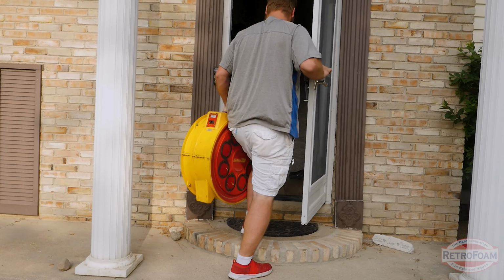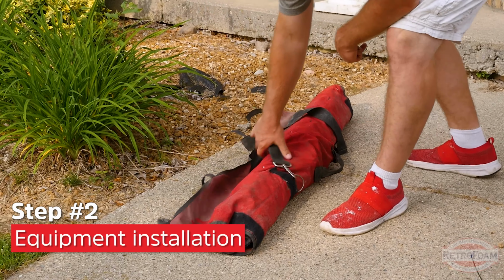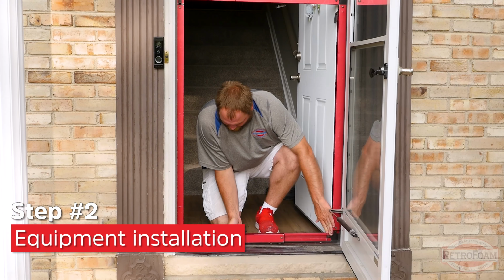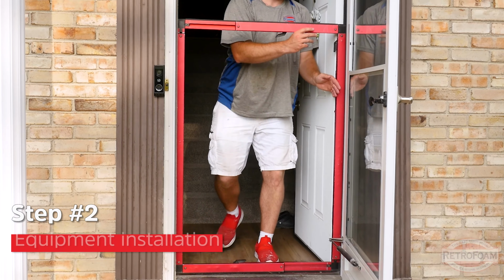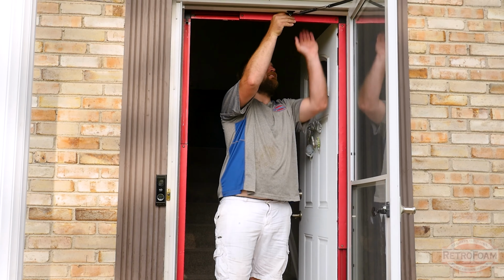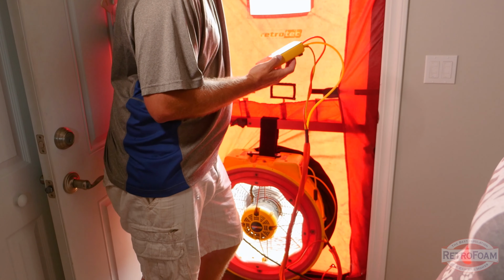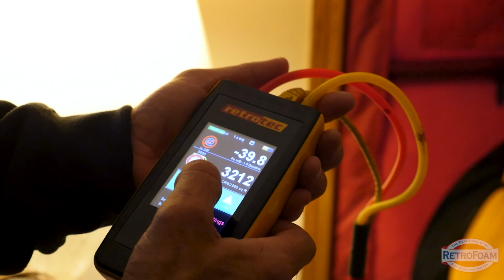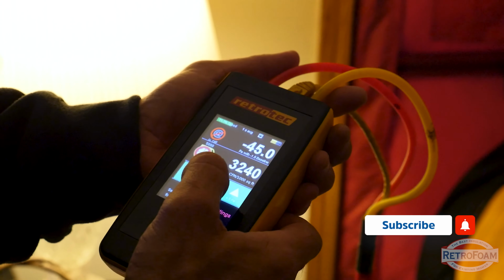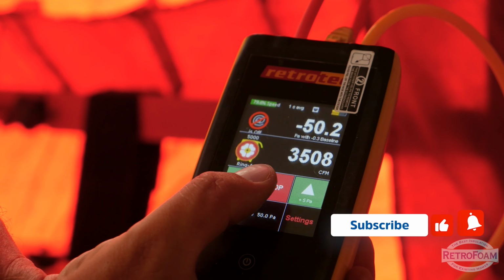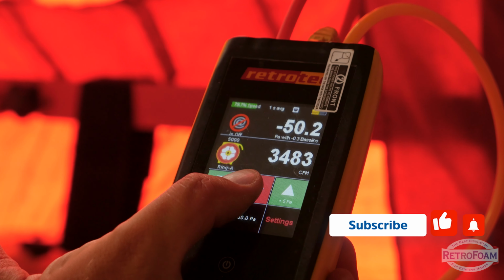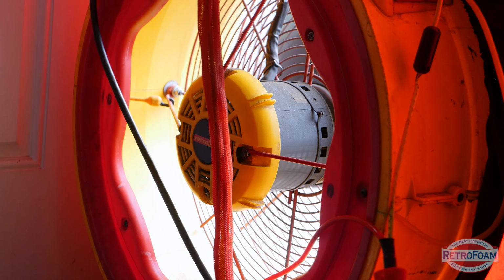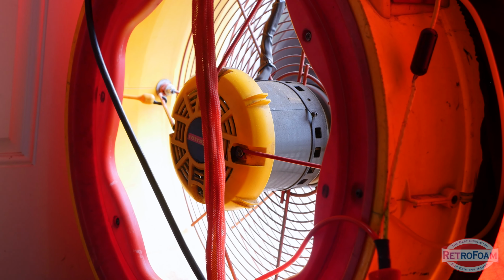Next up is the equipment installation. A frame and flexible panel are put together and then they're installed in the door frame. A fan is mounted in the panel, hooked up to a handheld pressure gauge and airflow meter. Once all of this is done, now it's time to run the test. The technician enters your home's square footage and sets the pressure to 50 pascals. The fan runs for 90 seconds to 2 minutes while airflow is measured in cubic feet per minute.